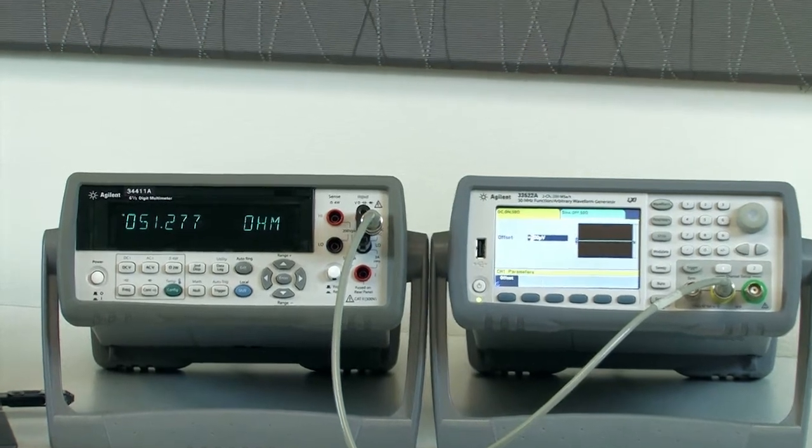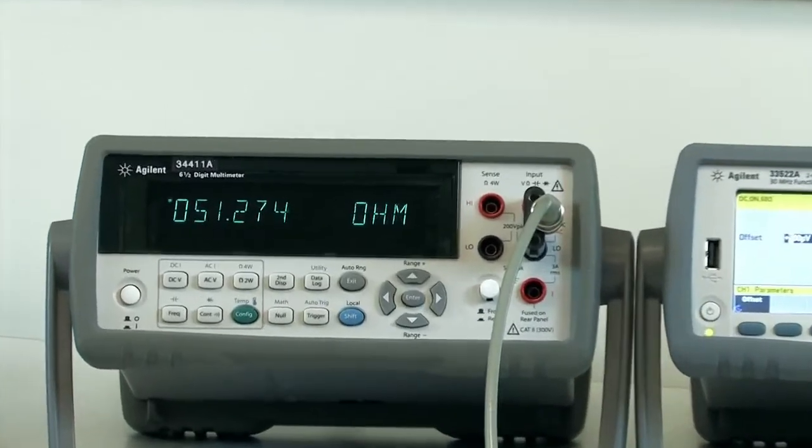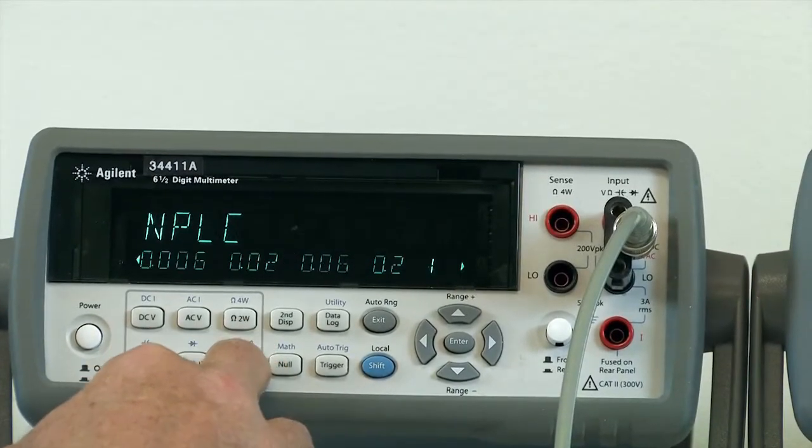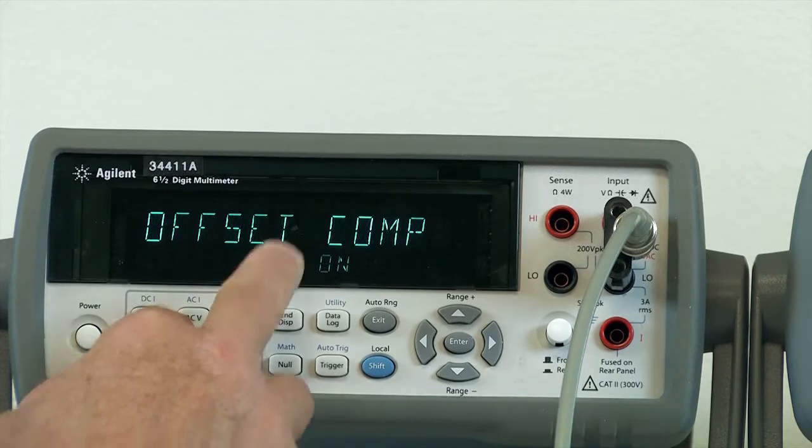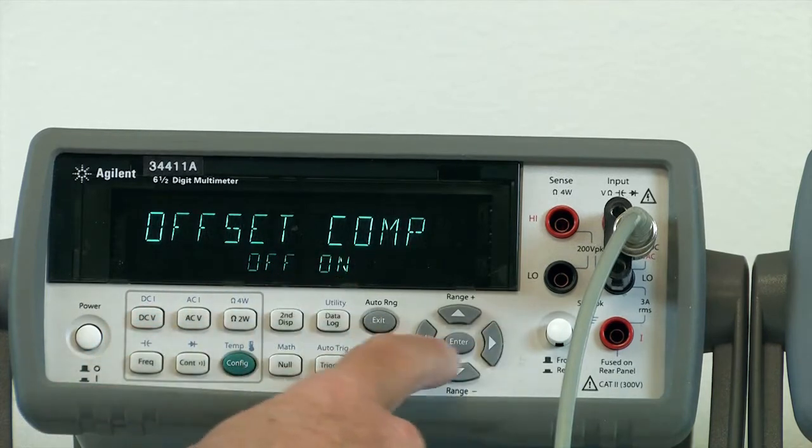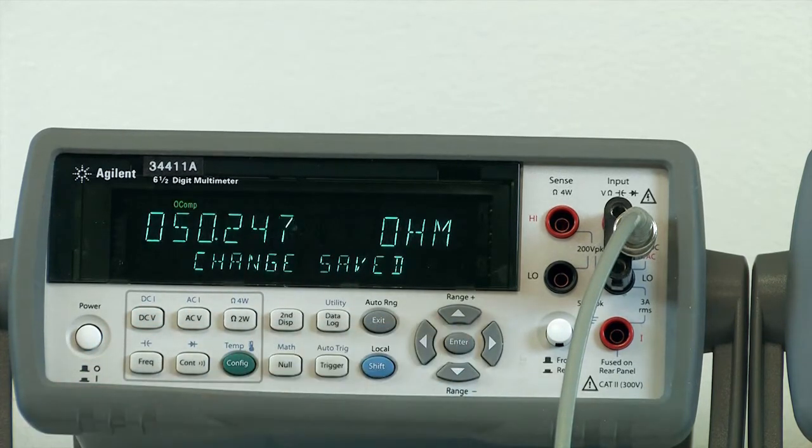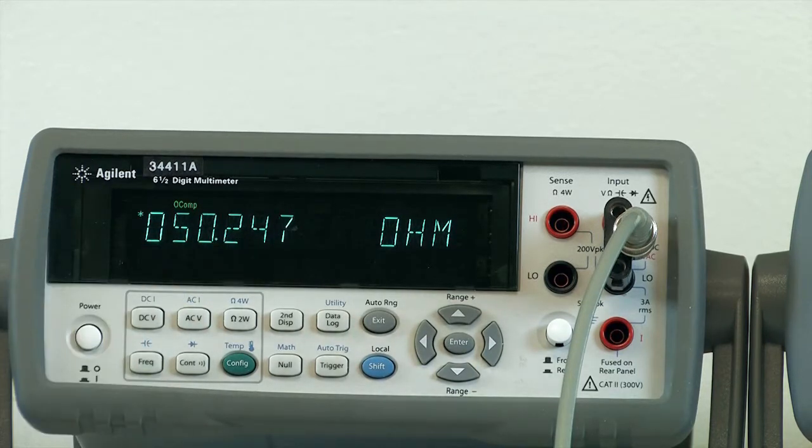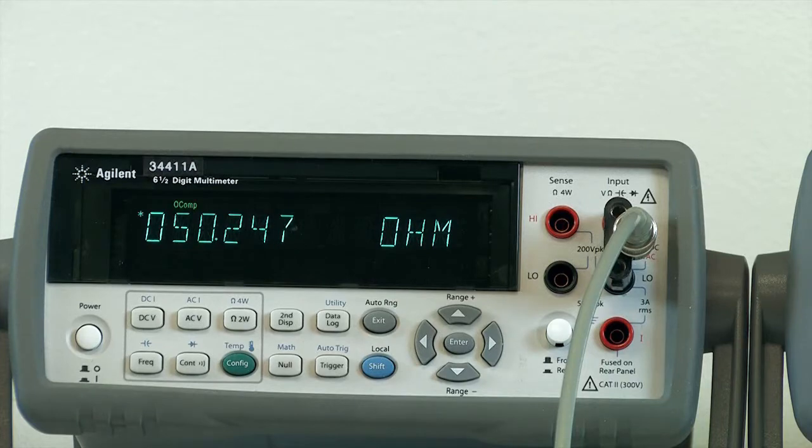Now when I turn on offset compensated ohms, the digital multimeter will compensate for that stray voltage. We go to offset compensation, turn it on, and now we see the little OCOMP indicator is on, and we see it's measuring again 50.2 ohms, just about the right measurement.